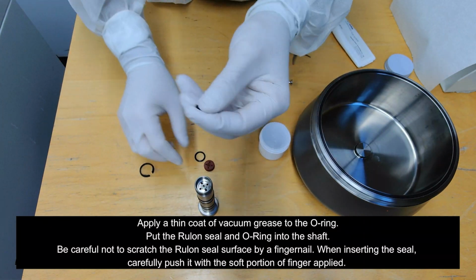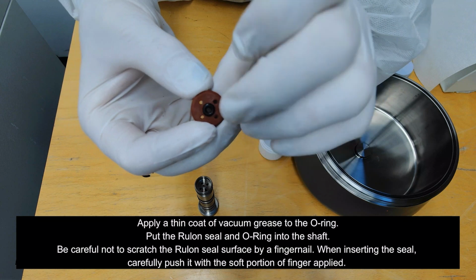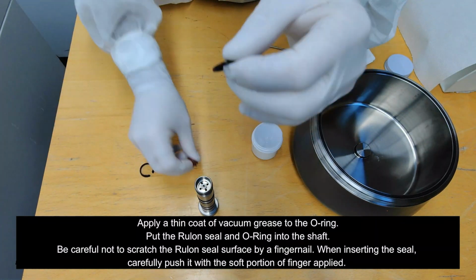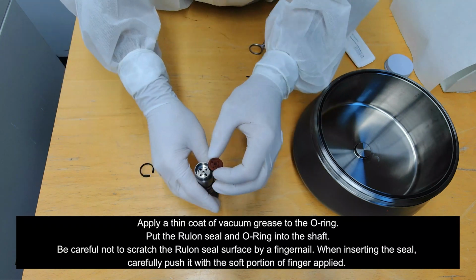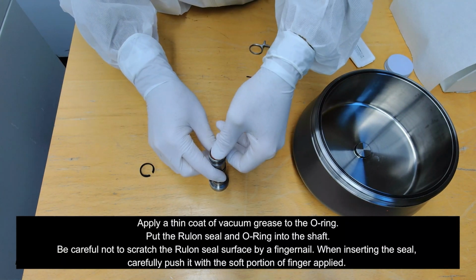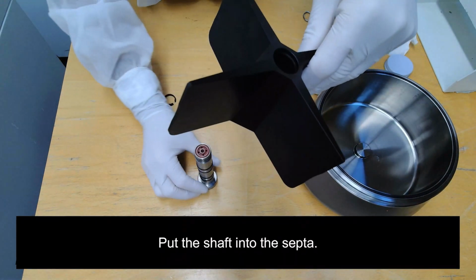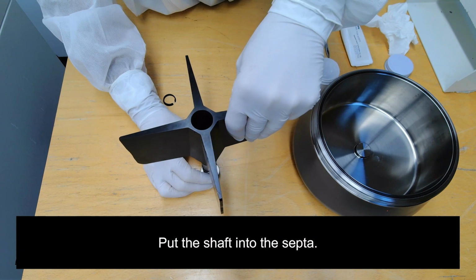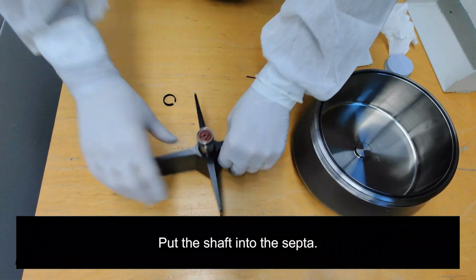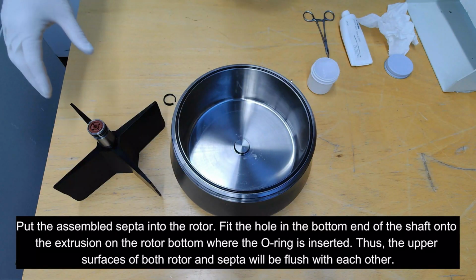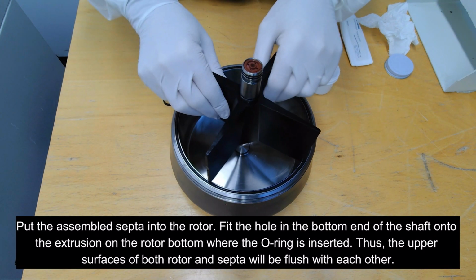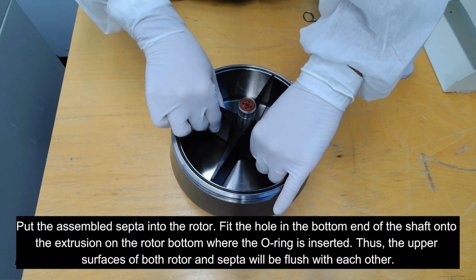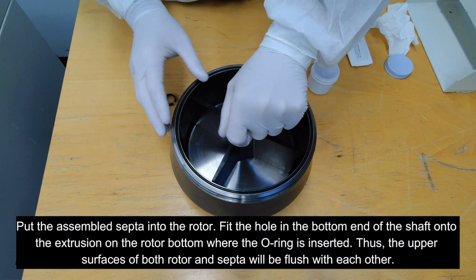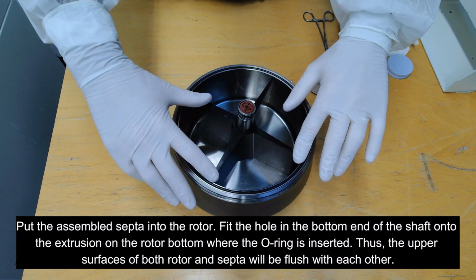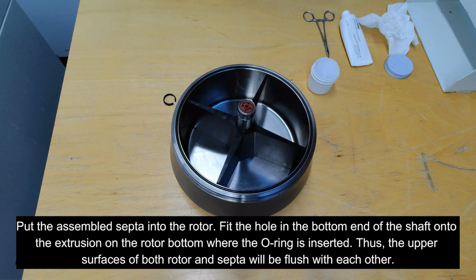Put the Rulon seal and O-ring into the shaft. Be careful not to scratch the Rulon seal surface with a fingernail. When inserting the seal, carefully push it with the soft portion of the finger. Put the shaft into the septa. Put the assembled septa into the rotor. Fit the hole in the bottom end of the shaft onto the extrusion on the rotor bottom where the O-ring is inserted. The upper surfaces of both rotor and septa will be flush with each other.